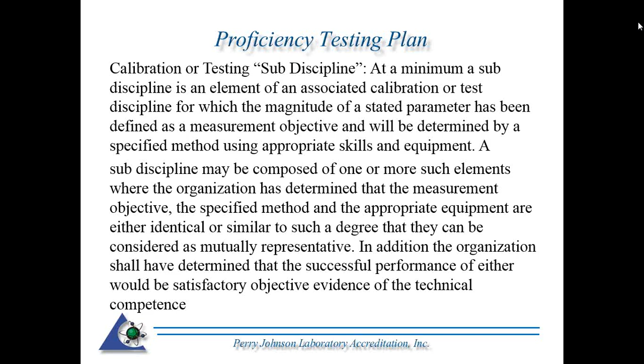So at the top there we have an example of a calibration lab. Under the discipline of dimensional, they calibrate micrometers, dial indicators, and calipers. So for the dimensional discipline, the organization has determined that the measurement objective, the specified method, and the appropriate skills and equipment used to calibrate micrometers and to calibrate calipers are either identical or similar to such a degree that they can be considered as mutually representative.